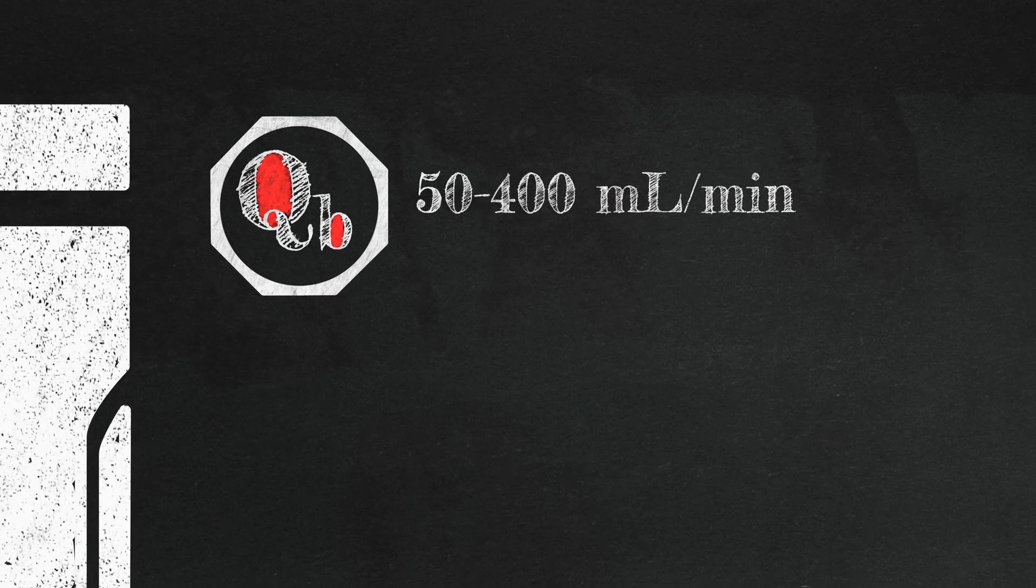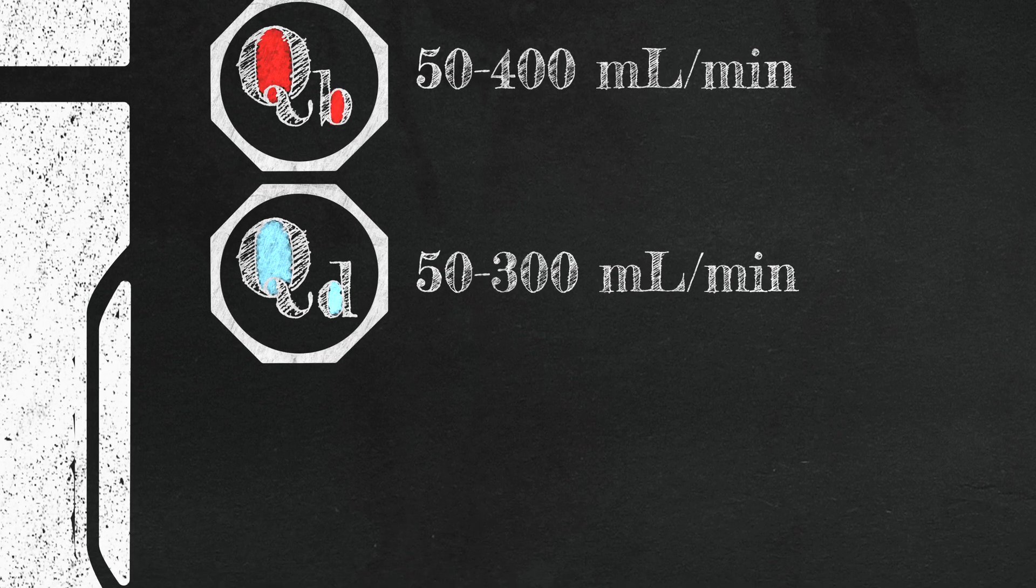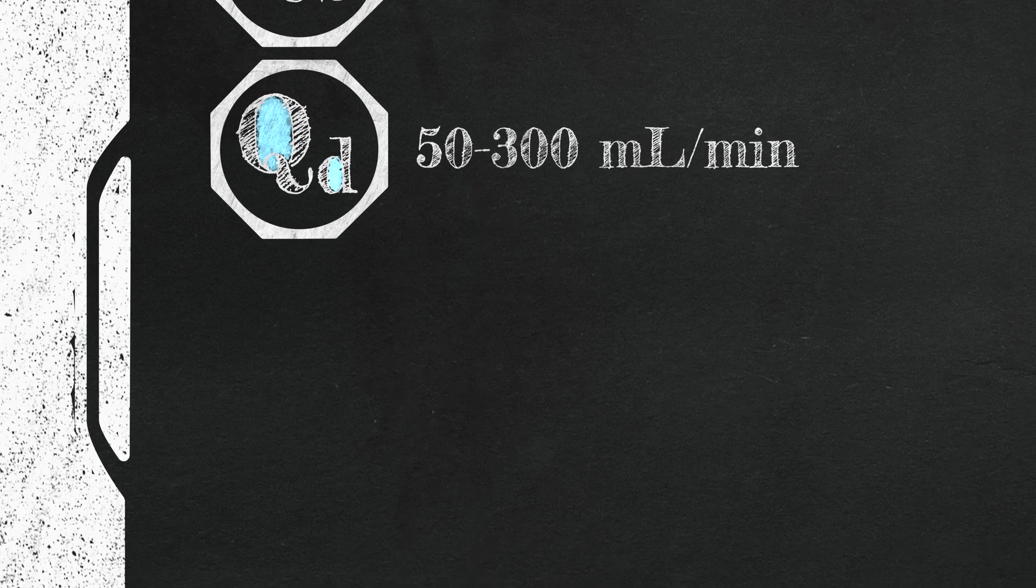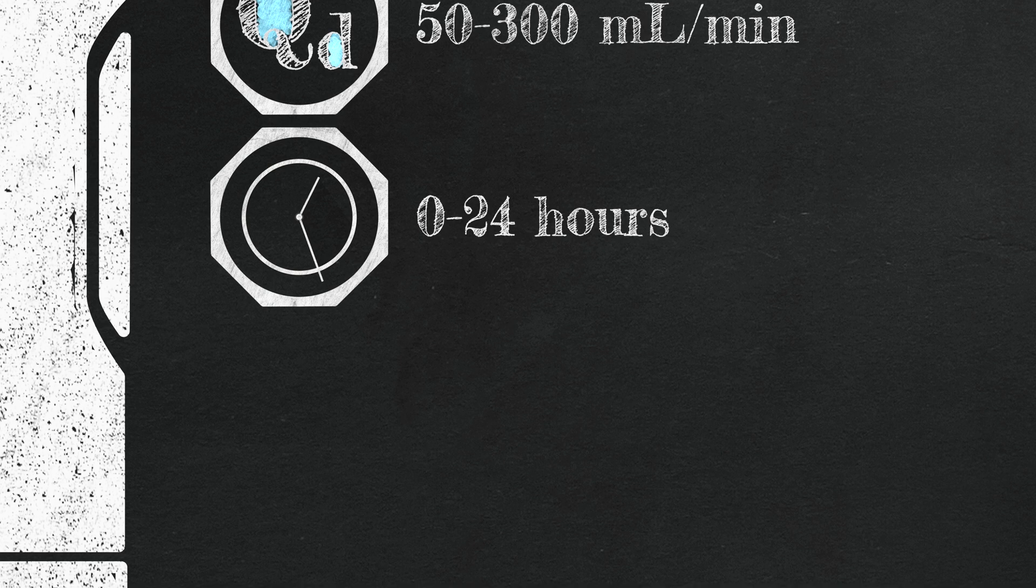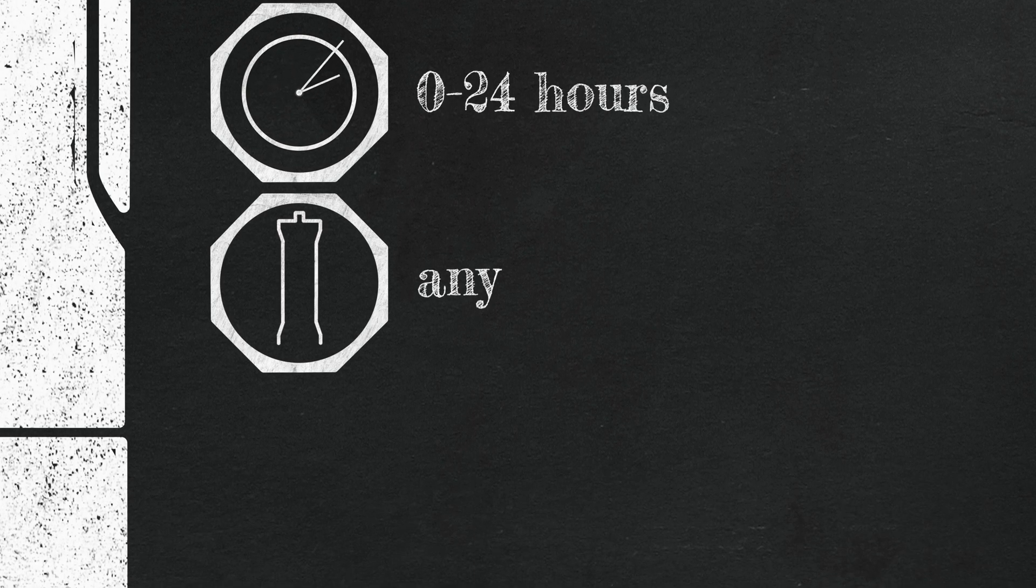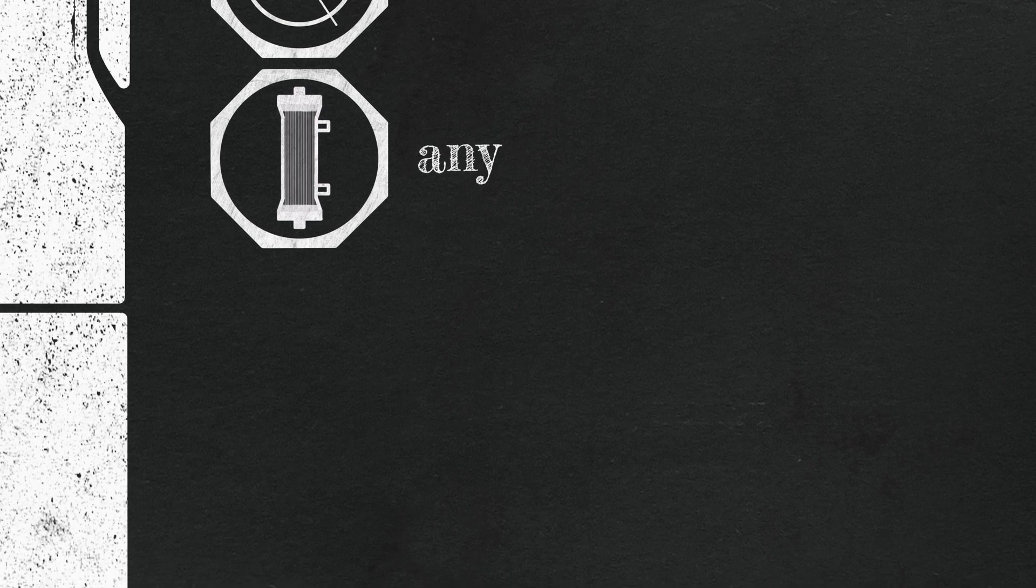Tablo Machine can run blood flow as low as 50 and up to 400 mLs per minute. Using water purification and proportioning system integrated in a compact form factor, it can generate dialysate flow up to 300 mLs per minute and run all day. It can use almost any standard high flux dialyser available, giving you the advantage to customize therapy to the patient needs.